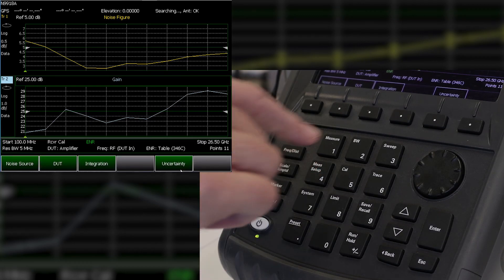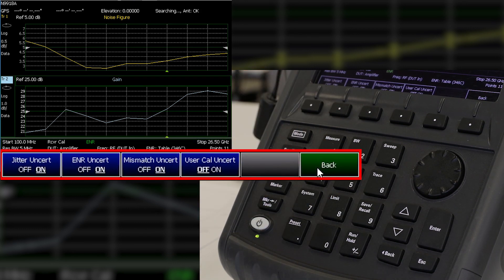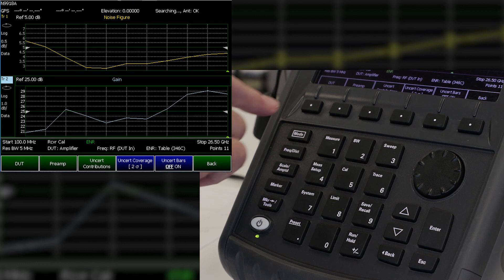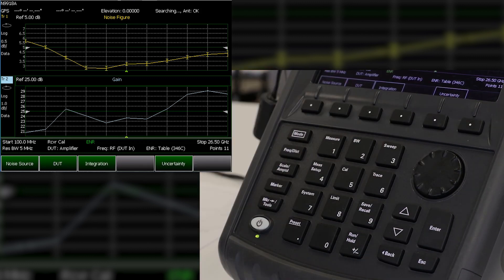FieldFox can provide real-time feedback on measurement integrity with built-in uncertainty bars that can be displayed on the measurement data. FieldFox can further determine uncertainty contributions due to jitter, ENR, mismatch, and user cal, and these uncertainty contributors can be turned on or off. Notice the uncertainty bars on each data point of the noise figure measurement that give you a visual display of real-time uncertainty values. These are unique noise figure measurement features that only FieldFox offers.